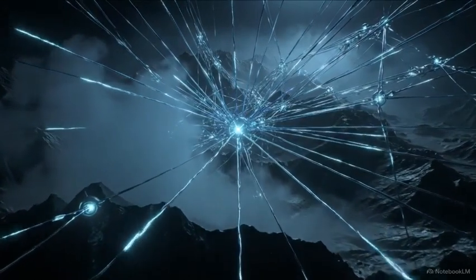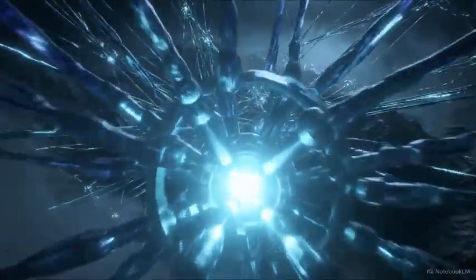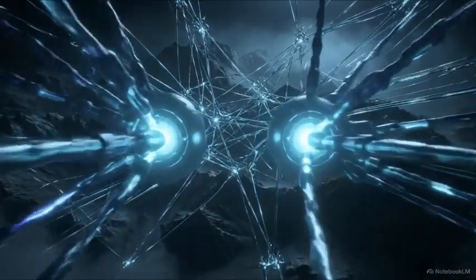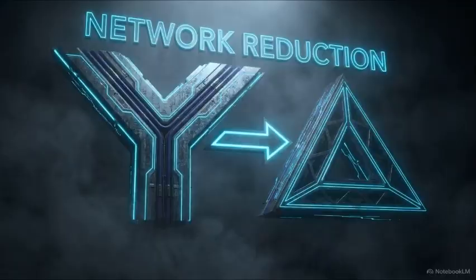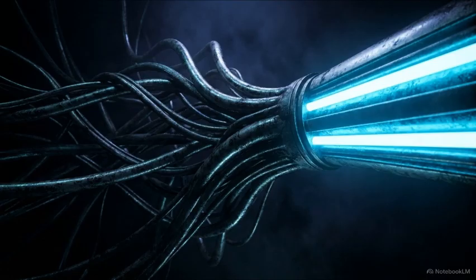Power grids consist of thousands of parallel lines and intermediate substations, creating a sprawling, complex web that is mathematically impossible to evaluate at a glance. To find the true stability limit of the entire system, engineers use star-delta conversions, mathematically reducing chaotic parallel lines and intermediate nodes down to a single equivalent transfer reactance.